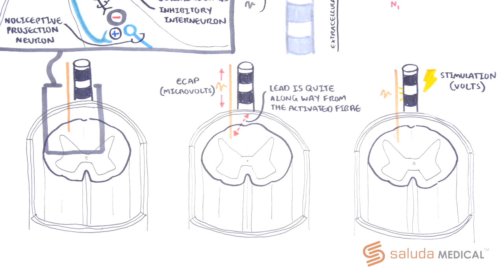The evoked closed loop spinal cord stimulation system is able to measure ECAPs in either direction, as they pass beneath the contacts on the epidurally placed lead, propagating away from the stimulus.